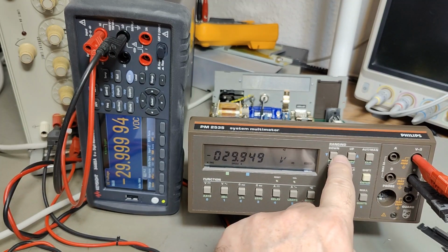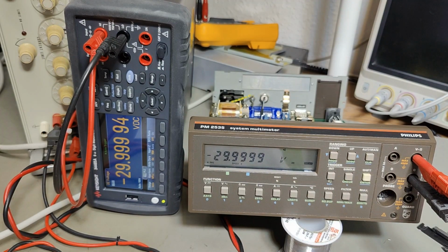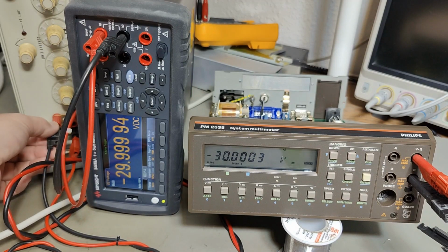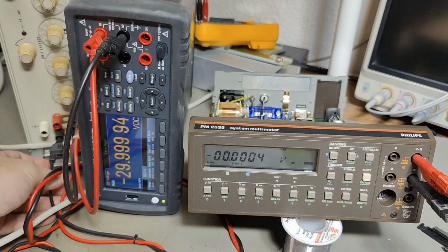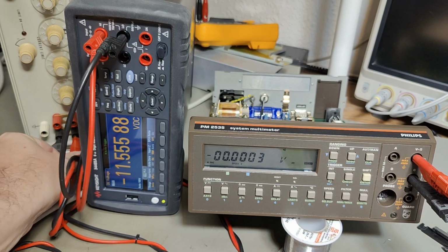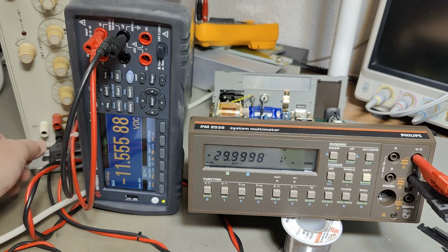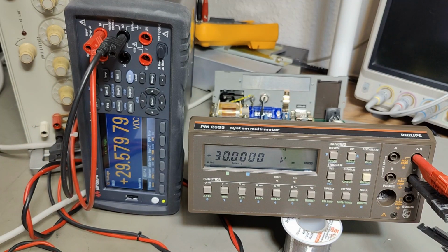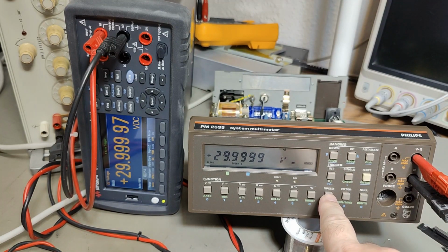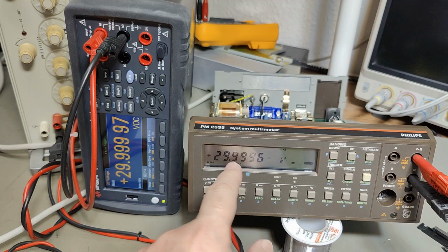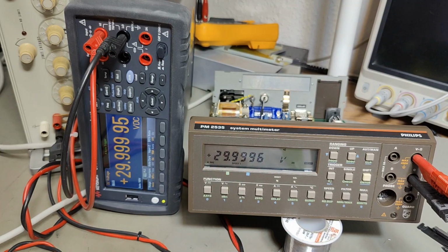So I have to go into manual mode and 30 volt range. And as you can see now, we have a very good reading of minus 30 volts. And I can of course go short the inputs, and I should have a very good 0, and I can go positive. So that should definitely make this instrument work if you're doing the calibration. And of course, if you want one more digit, you can hit the speed 1. It says here speed 1, and that means it's giving you one more digit after some time, like that, right?